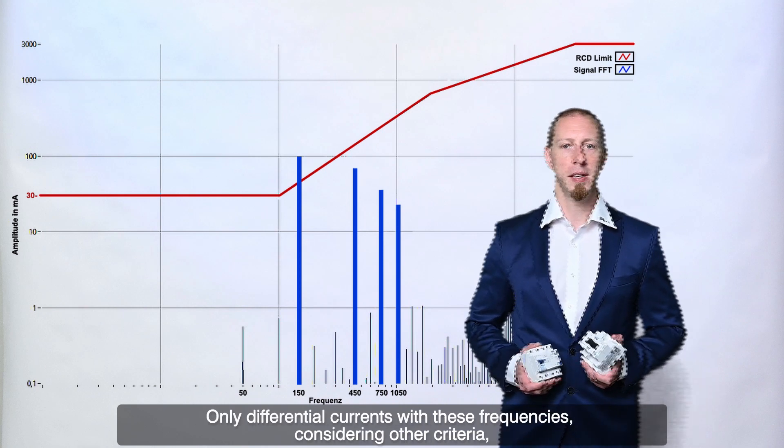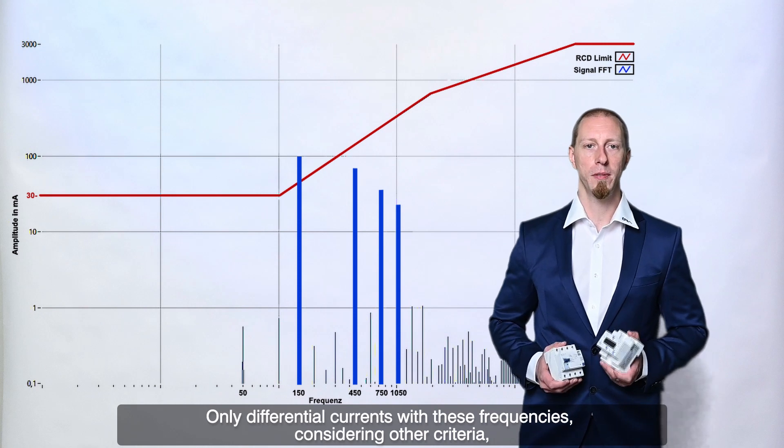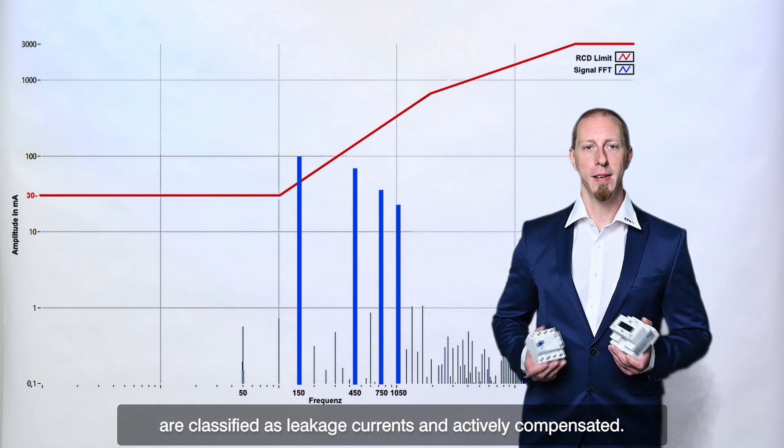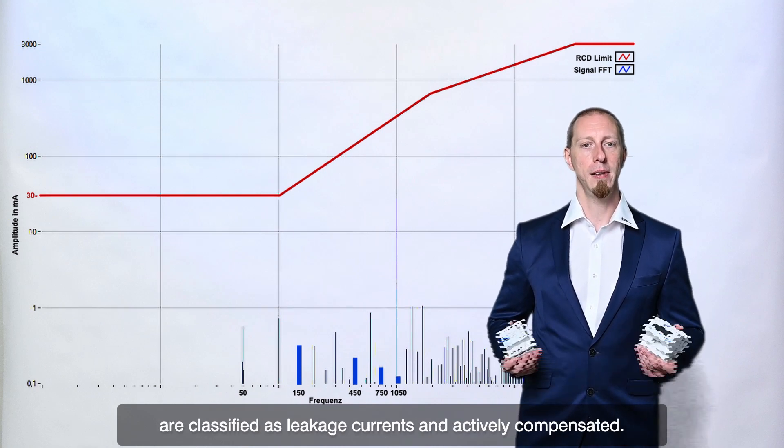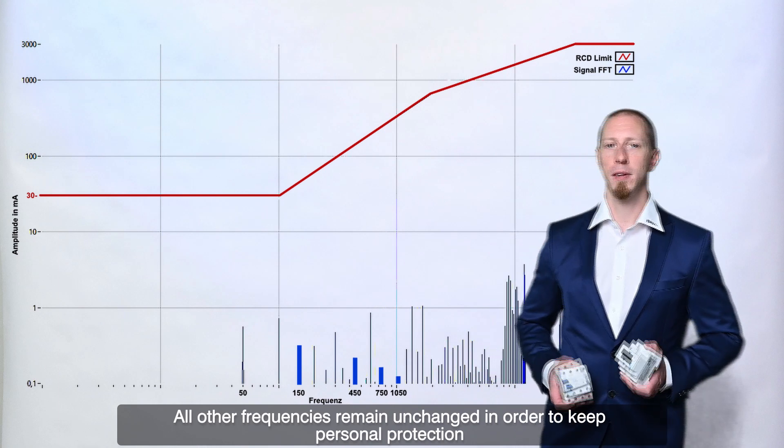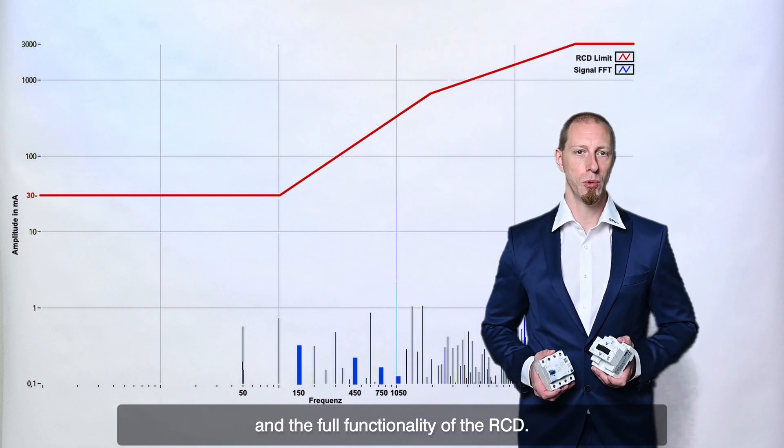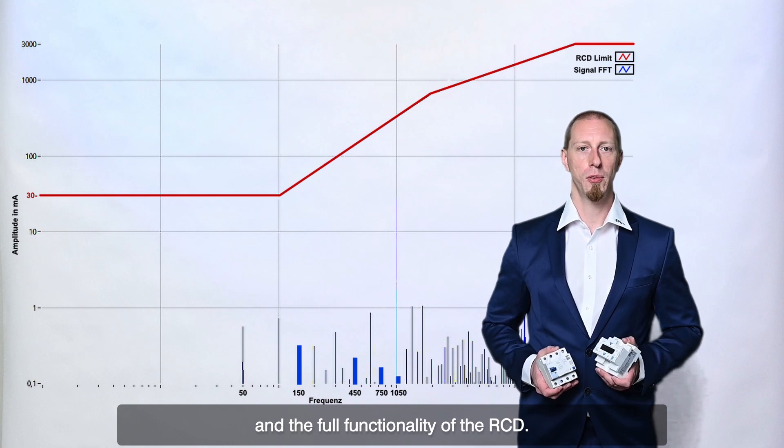Only differential currents with these frequencies, considering other criteria, are classified as leakage currents and actively compensated. All other frequencies remain unchanged in order to keep personal protection and the full functionality of the RCD.